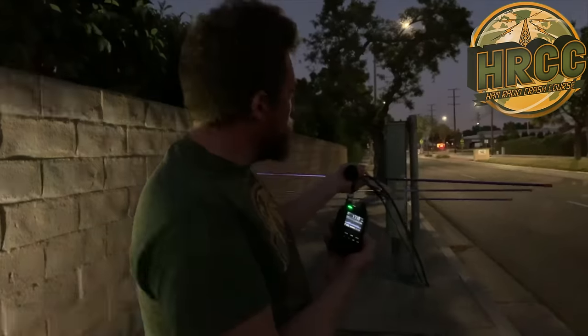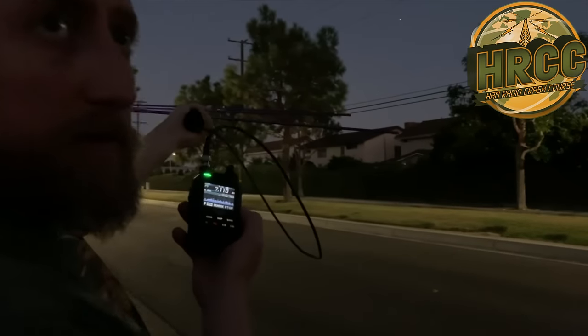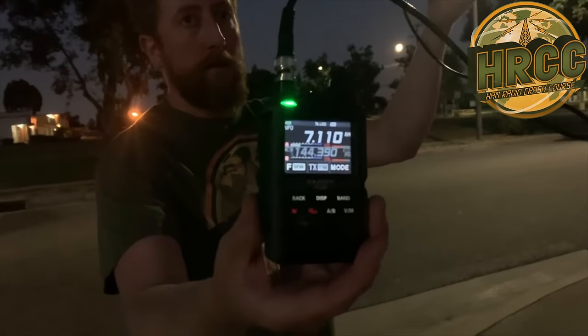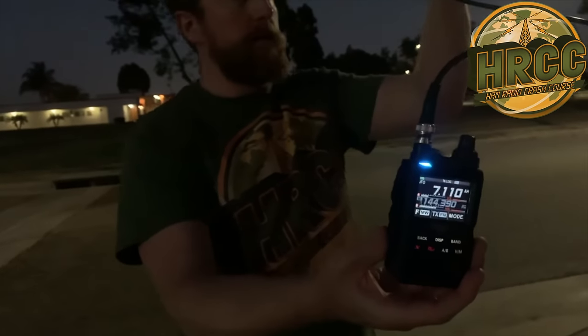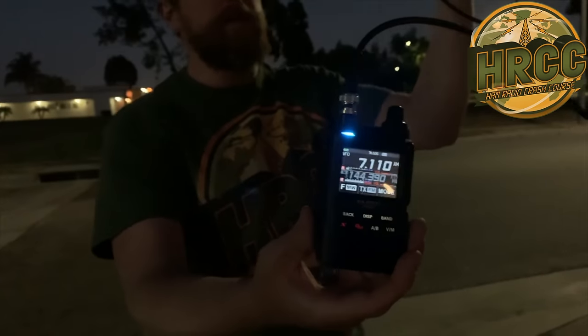The next step was to take out a Yagi. I used an Arrow antenna Yagi connected to a handy talkie that had an S meter and walked around my neighborhood like a weirdo, scanning around in a circular motion. I was able to find pretty quickly where the intense spots of RFI were. Here's the junction box around the other side of our wall pointing up to the power line that I think connects to it — we still have the noise. That power line — we've come about a block away, I'm pointing at the power line and you can still hear the noise. But then if I sweep over here, the noise is mitigated extensively. So it seems to be over on that power line side.